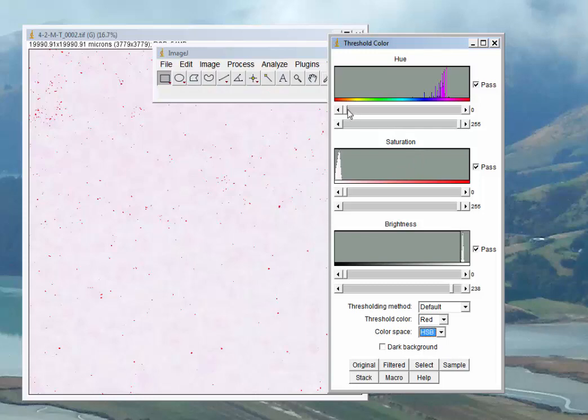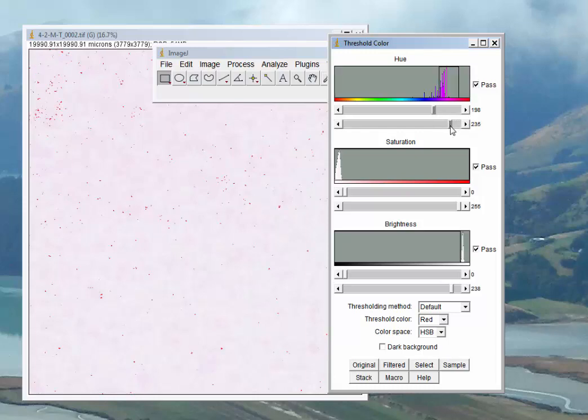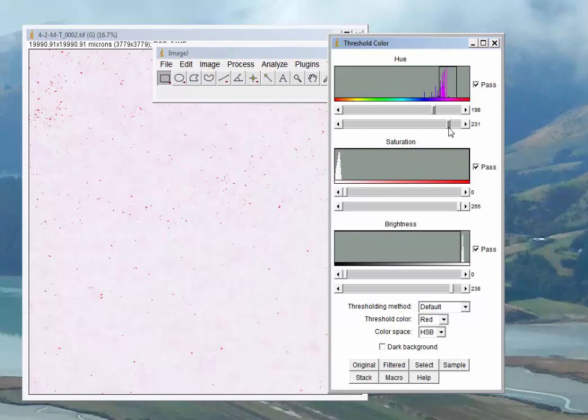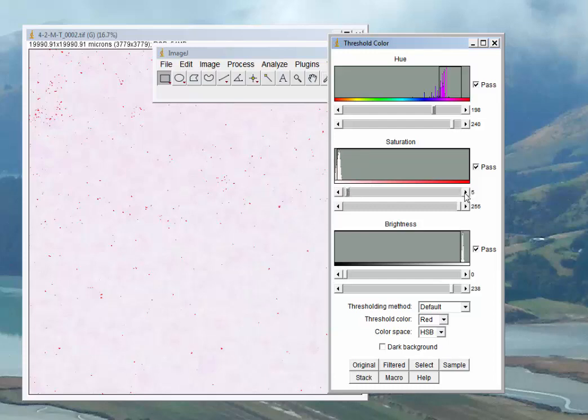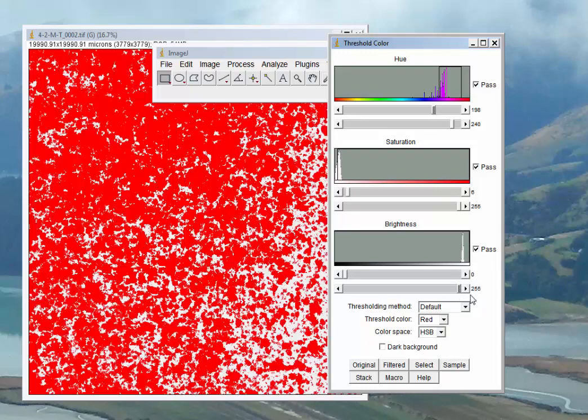We can see there's a lot of dye on this card already. We knew it was a reddish dye, and we can pretty much see the range we would want to capture that dye. We can use the slider bars in this window to make sure we've got everything. From our blank calibration, we know we want to be between four and six, so we'll set six and our brightness at 255.